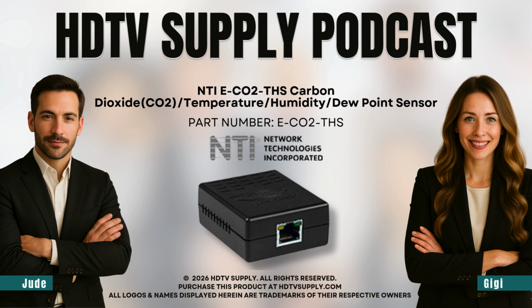It uses something called NDIR, single beam non-dispersive infrared, which is pretty much the gold standard for this kind of thing. It literally uses an infrared beam to measure the gas concentration. The cheaper sensors often use a chemical process that drifts over time. This NTI unit measures CO2 from 400 all the way up to 2,000 parts per million, and the accuracy is so tight you could actually automate your HVAC with it.